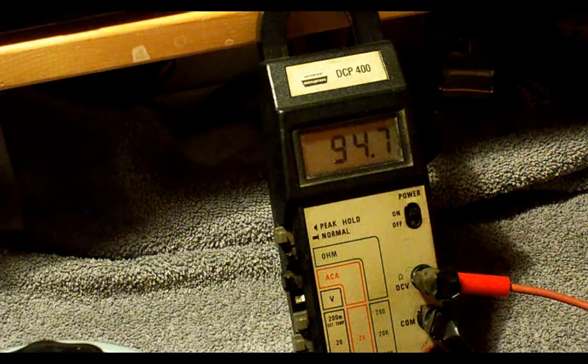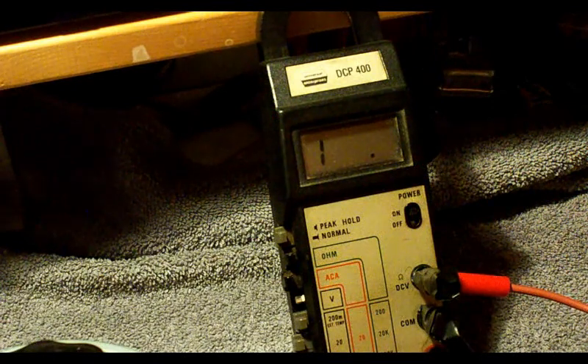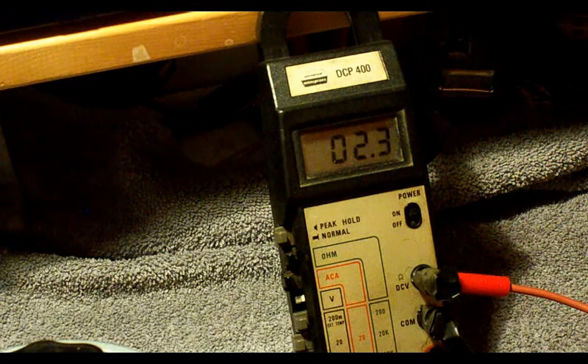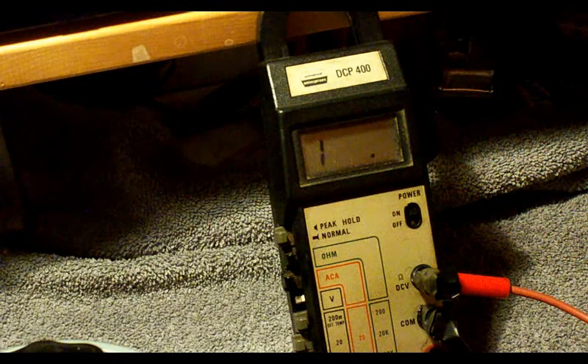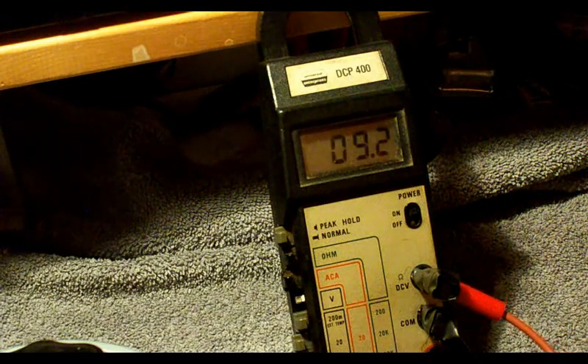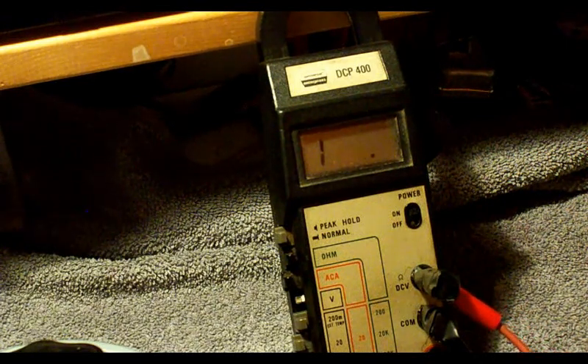Okay, we read about 94 ohms. That's good. Let's check across the secondary. We read about 2 ohms. And I misspoke earlier if I said that that resistance reading on the secondary was higher. It's actually a lower resistance, which would be normal since it's got less turns in it. So we read about 2 ohms there. That's good. Now the defective transformer, let's check the resistance on the secondary.